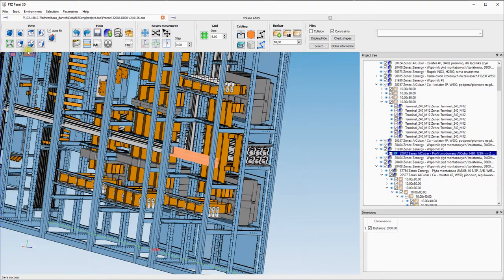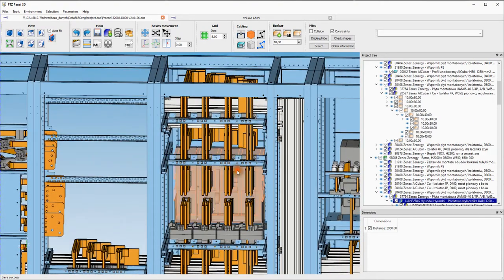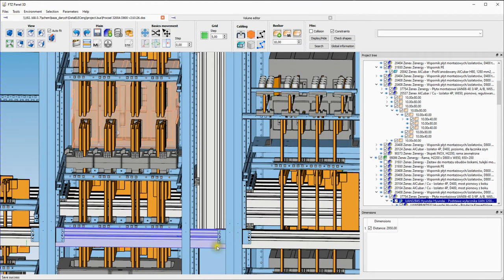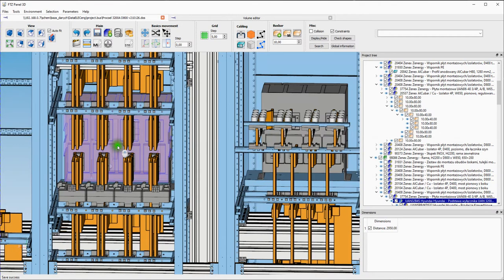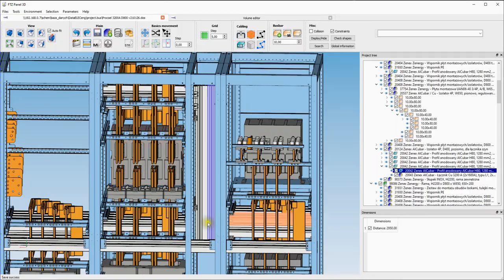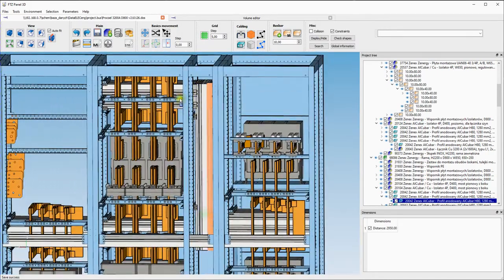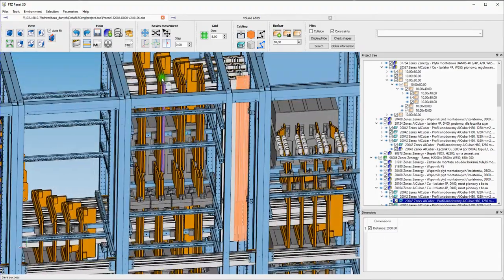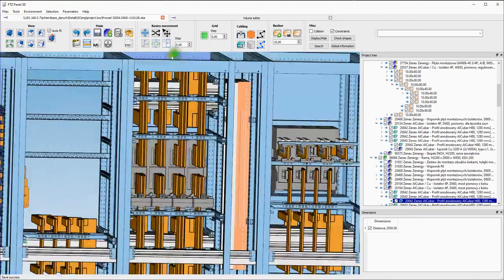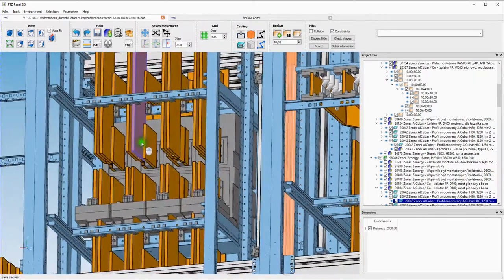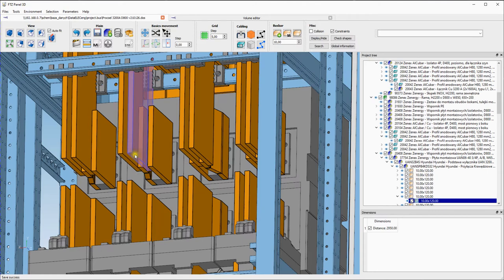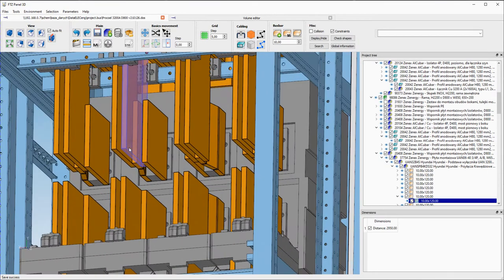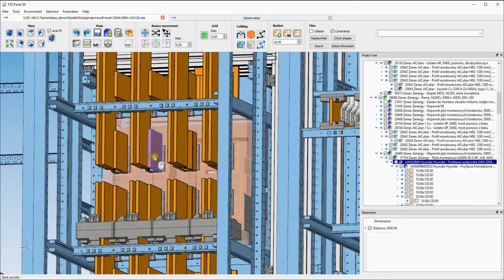Next is the field with the 3200 ampere breaker, and as you can see the main duct comes here. Okay, so 3200 is here. The main bus bars are coming here horizontal, later some small part vertical, and all the bus bars are going to the top. From the top the main 3200 ampere has 120 by 10, 2 bus bars for each phase, so it's 2400 square millimeters for 3200 breakers, so it's very nice.